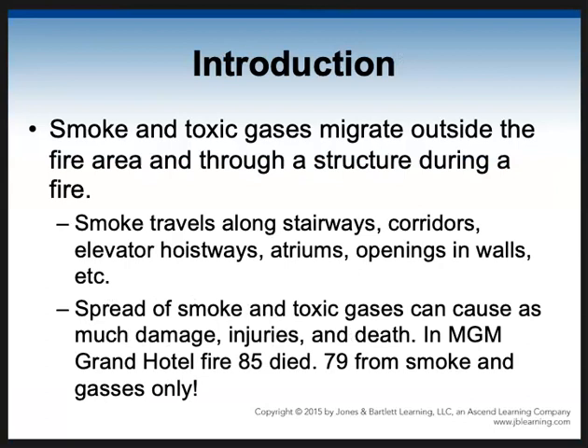So, smoke and toxic gases are going to migrate throughout the fire area, even when we have a very small fire, but it can be in something that's very hazardous and spreads toxic gases and smoke particles throughout the building, which are extremely dangerous for human beings. So the smoke is also, we know heat rises, and the smoke goes with the convective flow, and it'll go up stairways, corridors, hoistways, and of course, if we have an atrium or some kind of an opening, it's just going to flow from one floor to the next. So the spread of smoke and toxic gases is usually what kills people. It can cause as much damage and injuries and death.